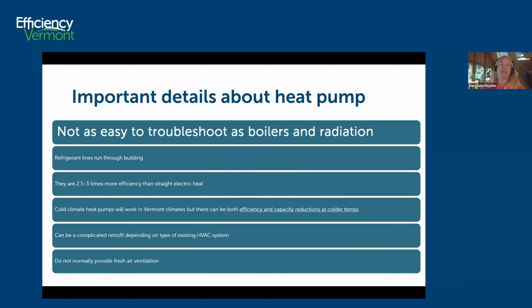A few important details about heat pumps that I would want to communicate to my customer before moving forward. Number one, heat pumps are not as easy to troubleshoot as boilers and radiation. So if I have a customer that right now has a couple boilers, pumps, baseboard radiation, zone valves, and thermostats, it's easy to troubleshoot if you have a problem. Are your boilers running? What temperature is the water leaving the boilers? Are your pumps on? Are your zone valves opening and closing? That's pretty much it. But with heat pumps, it's not as easy to troubleshoot.